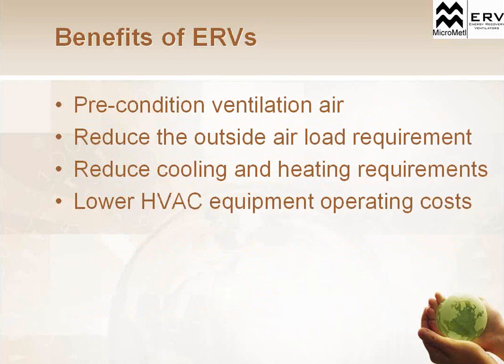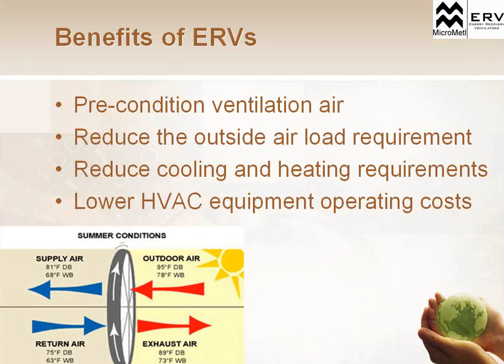We'll use a diagram. So what we're going to do is precondition ventilation air. We're going to reduce an outside air load requirement. We're even going to reduce cooling and heating requirements, and I'll explain how we do that. And also we're going to lower HVAC equipment operating costs. Now to explain that, I'm going to show you how a wheel works. Typically, an energy recovery unit in the commercial marketplace is used in a wheel, an energy recovery wheel. We'll go into that detail later, but just for the sake of this diagram, this is basically how an energy recovery unit works.